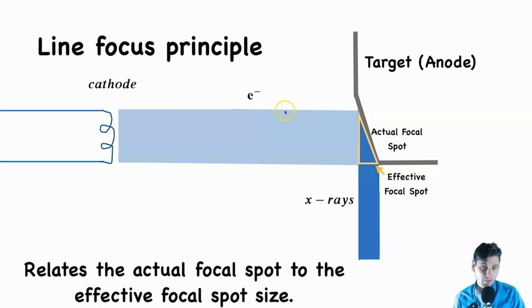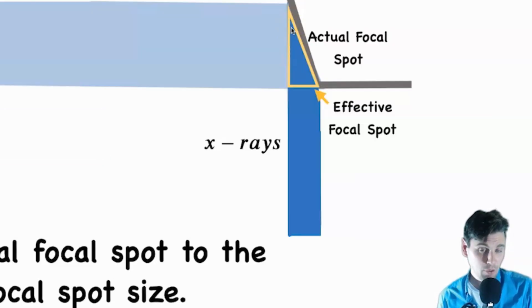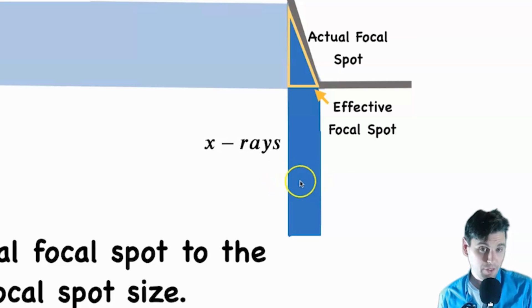The idea is we have electrons coming in, and if the width of the electrons can be larger than the width of the x-rays, what we call the actual focal spot on the anode can be bigger than what we call the effective focal spot — the size of the x-rays coming out.